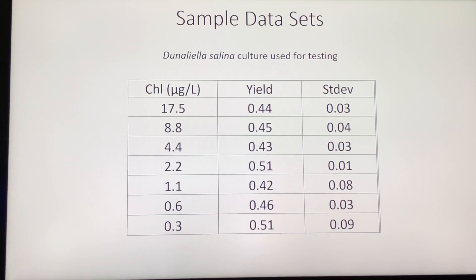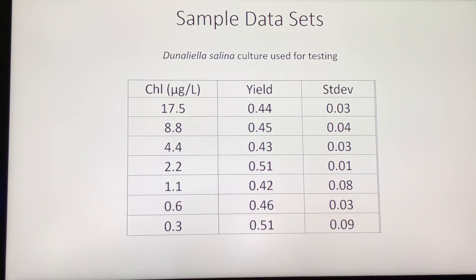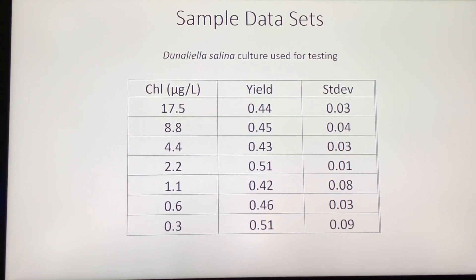This data set shows yield values across various chlorophyll concentrations. The concentrations were made by diluting a parent culture of Dunaliella. Although the concentration dropped to near minimum detection limits, the yield parameter is unchanged, telling us that Aquaflash provides reliable yield estimates even at really low algal concentrations.